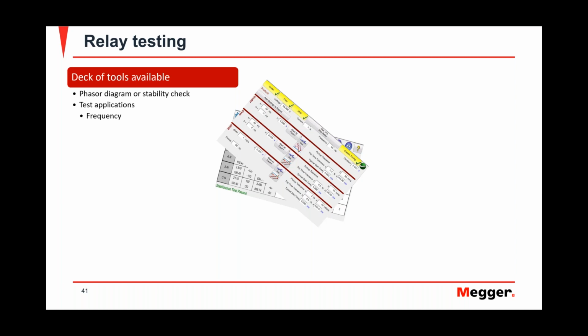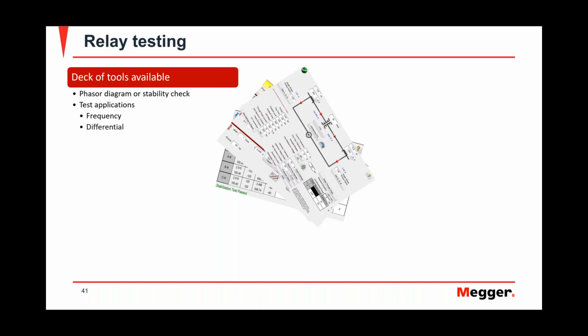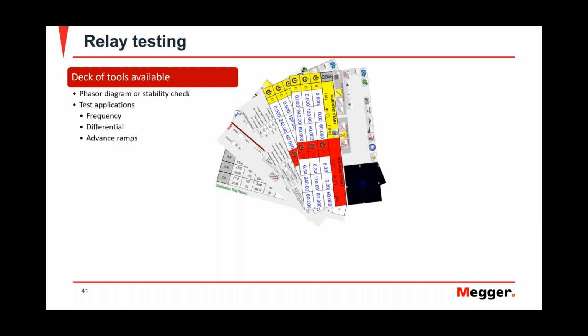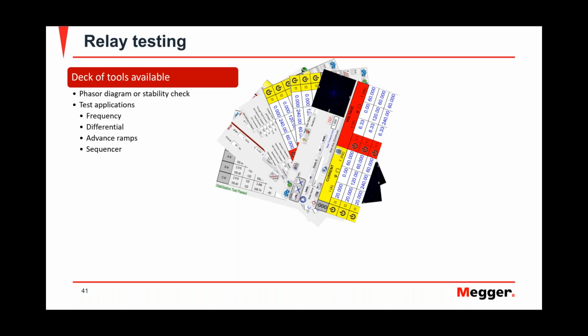You could have other tools that check for frequency. It will do everything: your under frequency, over frequency, your rate of change of frequency. There are differential tools for motors, transformers, bus differentials. You have advanced ramps; knowing how to use ramps and how to set them together to test. You could use an advanced ramp to test a 25 element, and you want to check the angles on both sides, the positive angle and your negative closing angle. You could do one test instead of two to test the positive and the negative and the pickup, all using one ramp. The sequencer is a good tool when you want to test reclosers.